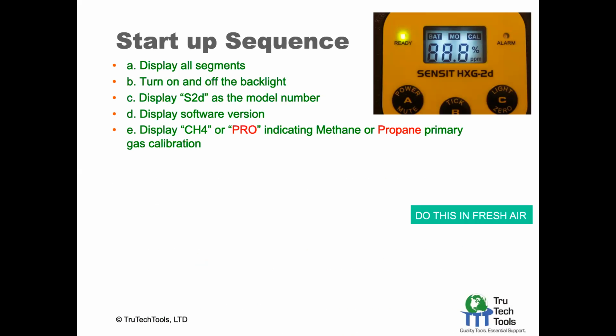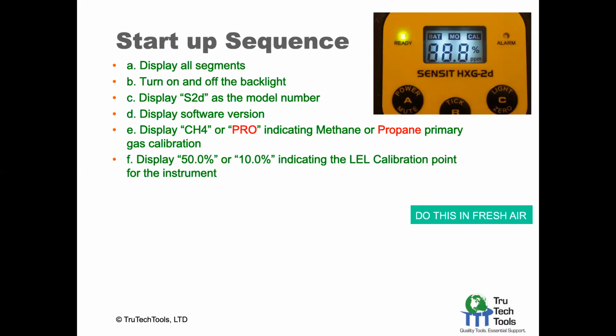It'll display CH4, which is the chemical abbreviation for methane, or PRO, to indicate that it's calibrated primarily to propane gas. So that's where you can tell, because there's really no outside marking on the unit, that it would just be in the display when you power it up. It'll also display if it's at 50% or 10%, indicating the LEL calibration point, and the ones you'll have will be at 10%. And then also indicating whether it's resolving ppm, percent LEL, or both.